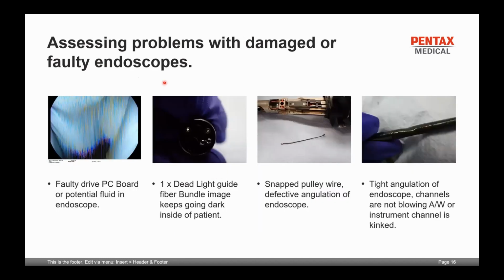Okay, so, assessing problems with damaged or faulty endoscopes. What I'm going to do is show you a series of images that you might come across during your inspections of the endoscopes, to help guide you in the way that you need to assess it. So if you have a look at the first image, this is a video image that has become faulty. 9 times out of 10, a faulty image like that has occurred because of fluid contamination to the endoscope, which could then have a faulty drive PC board or a faulty CCD chip or CMOS chip.